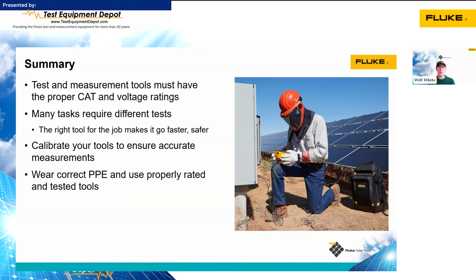Now, in this picture, this technician has all the right equipment. They've got electrically insulated gloves, FR-rated clothing, their arc flash face shield, the balaclava, and yes, he is kneeling on the ground. That's not necessarily a best practice because his knee is making a lower resistance path to ground than the sole of his rubber shoes are. So it would be better to be crouching there instead of kneeling. But he's got all the right equipment on, which is really the key in this case.